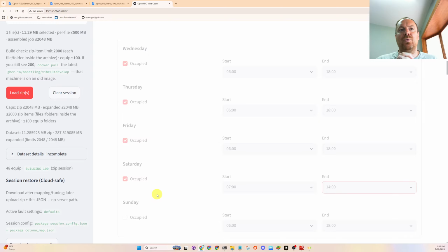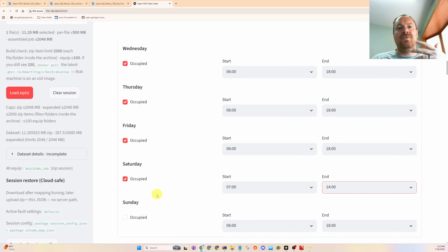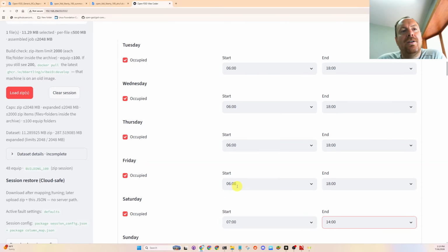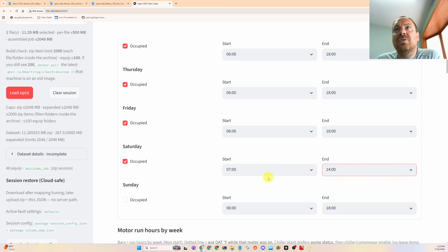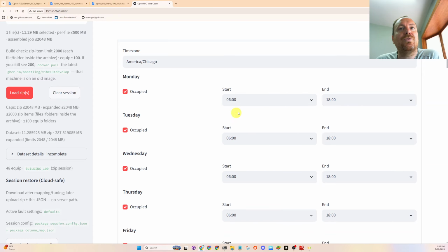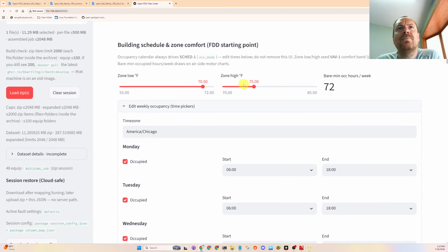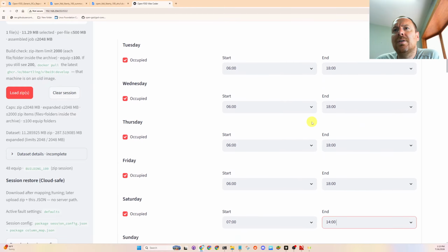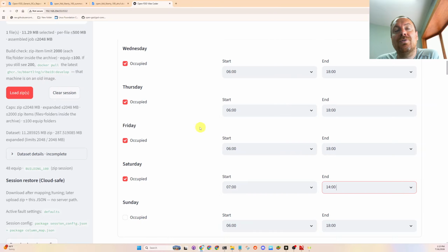So I'm just re-inputting the schedule for the building. This is the schedule that the owner is required, per leasing agreement, to keep the building conditioned from these hours to these hours. And then it's up to us in HVAC optimization to put algorithms in place that bare minimally run the building beyond this. Part of the strategy is that the building automation system would be a perfect mimic of this Monday through Friday schedule from the leasing agreements, the 72 degrees Fahrenheit requirement, and that we would have optimal start algorithms so that if equipment needs to run earlier, it can.